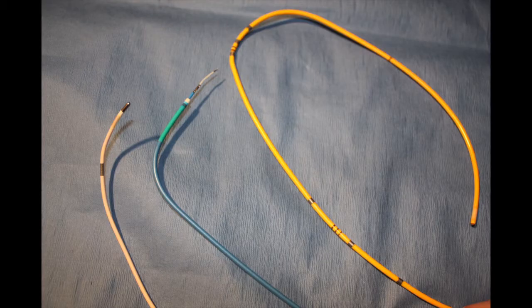Here's an example of 3 different pacing catheters. The white is a balloon tipped. The blue is a screw tip, and it should always be placed with an attending supervision. The yellow is a pacing swan.